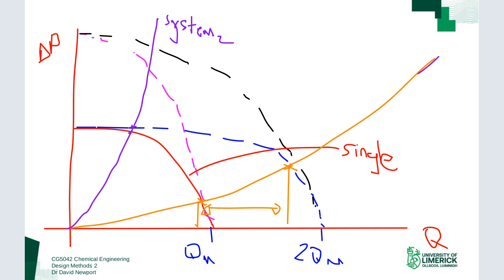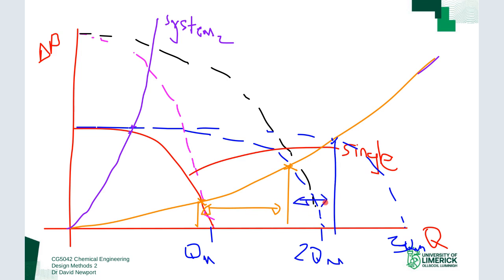If you get greedy and add a third pump in parallel — going to 3Q_M — you can see diminishing returns on the change in flow rate. You get an initial gain on low-pressure systems, but as you keep adding pumps in parallel you get diminishing returns.